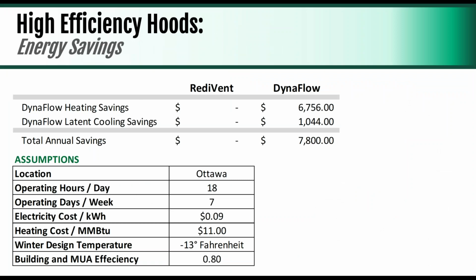So when we look at high efficiency hoods, we calculate the energy savings. So our RediVent is the baseline. There's a little lower capital cost up front to do those, and we'll go through payback in a little bit. But the Dynaflow, just looking at the energy savings, between heating and cooling, we're going to be saving almost $8,000 a year.